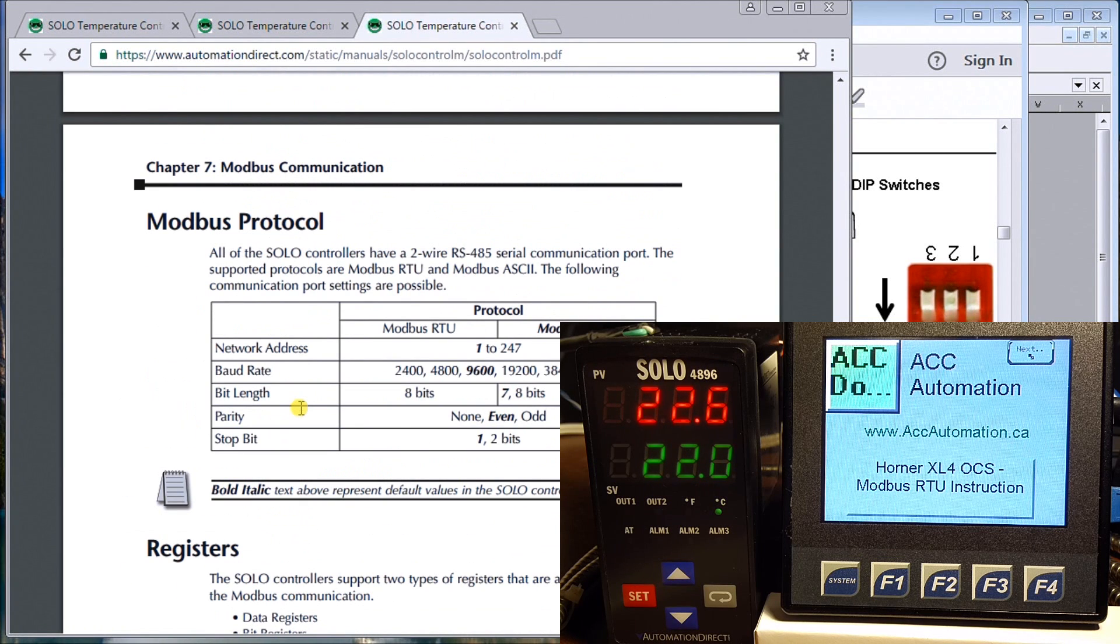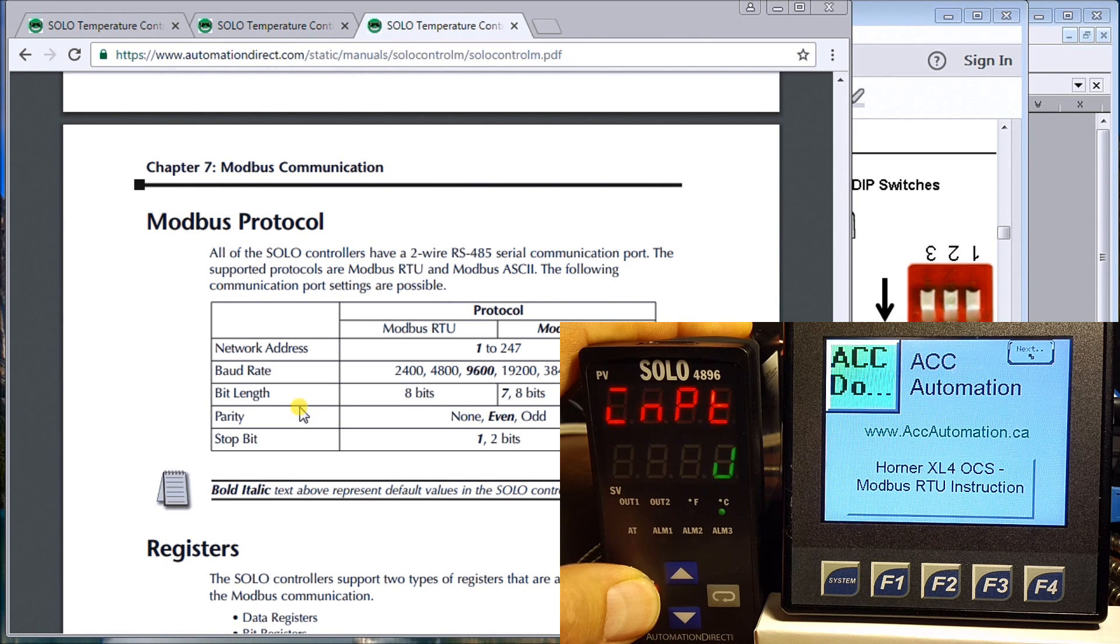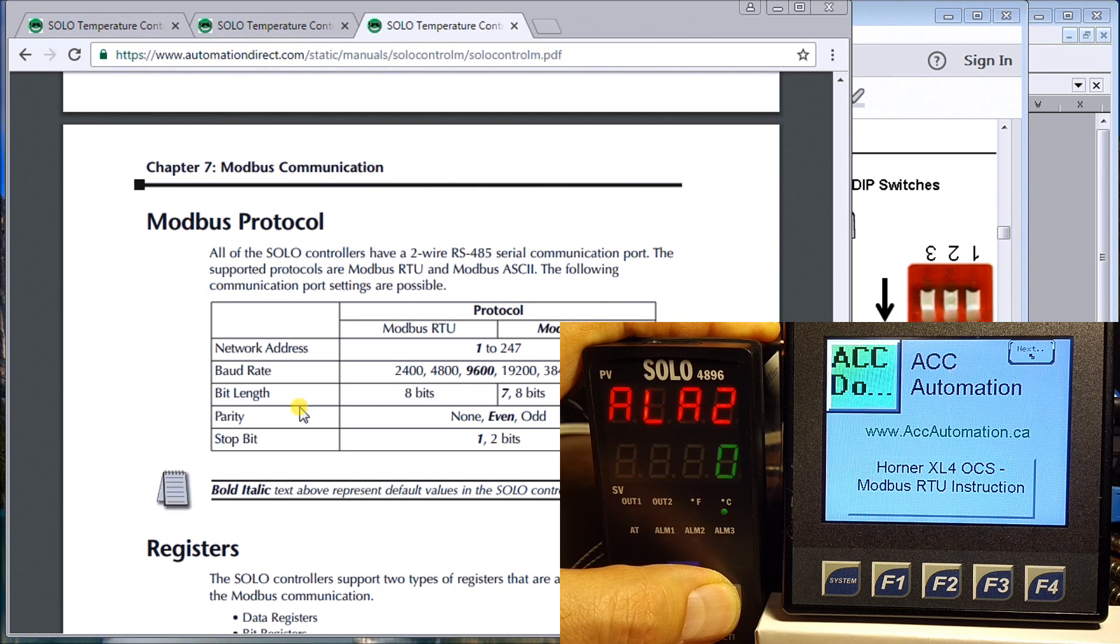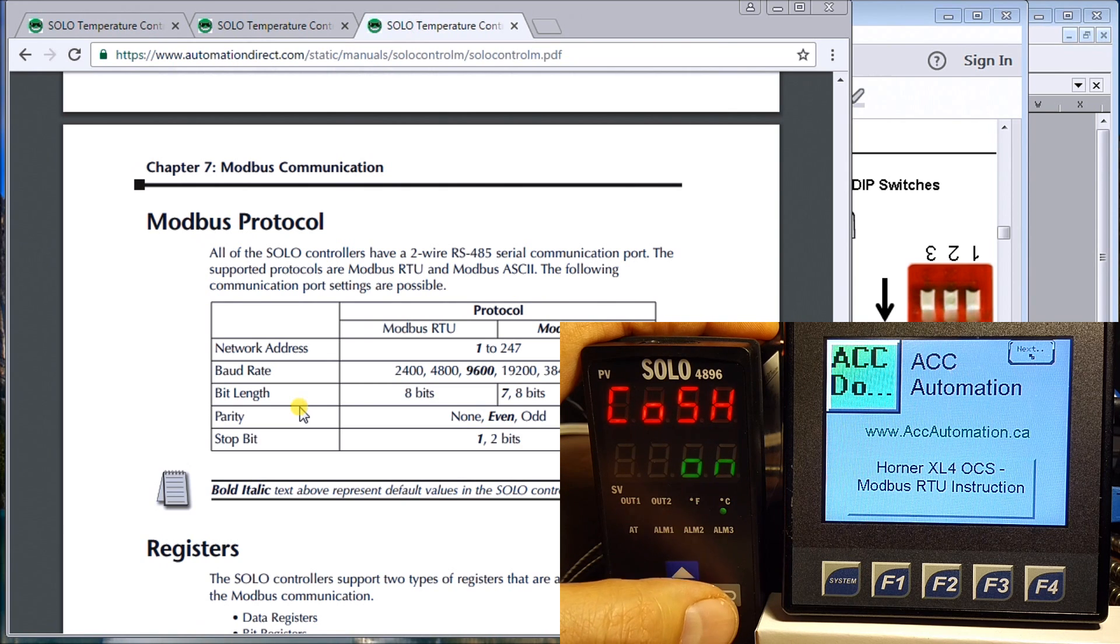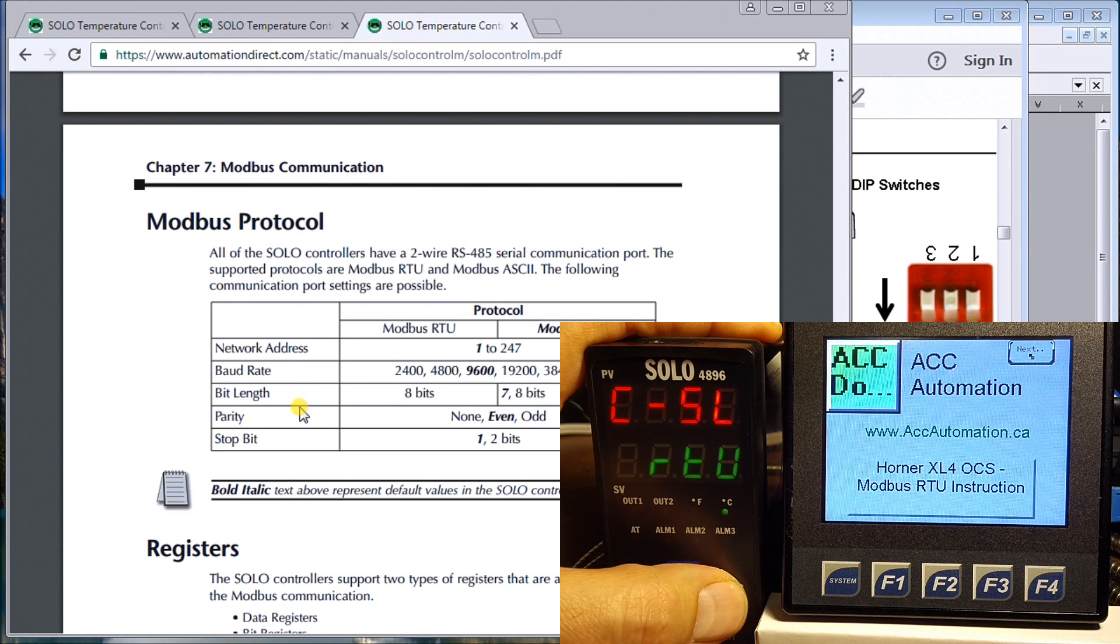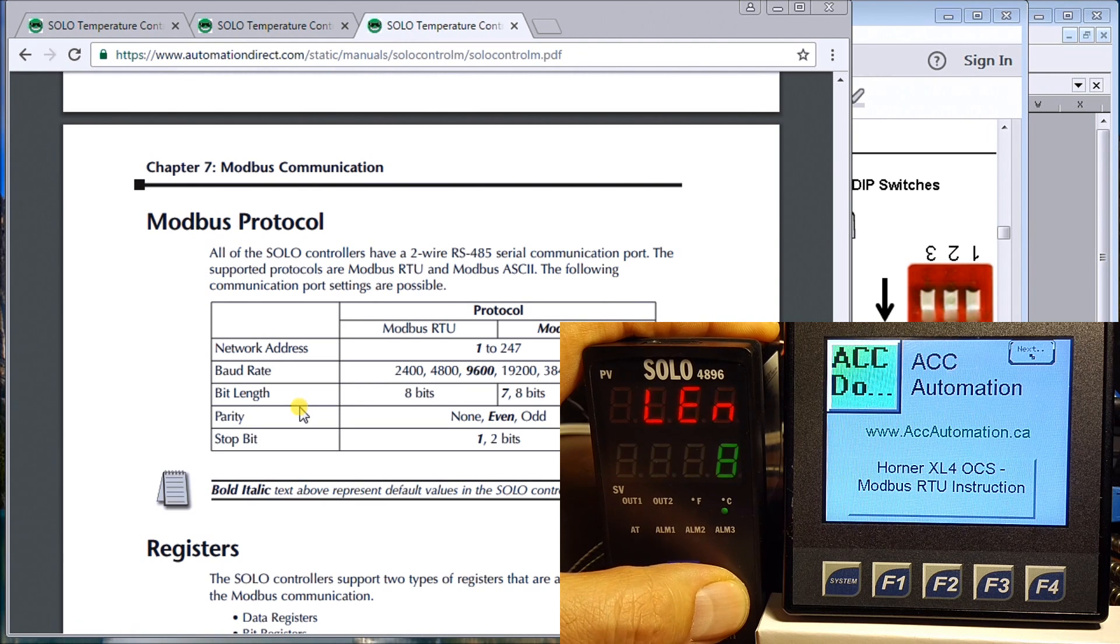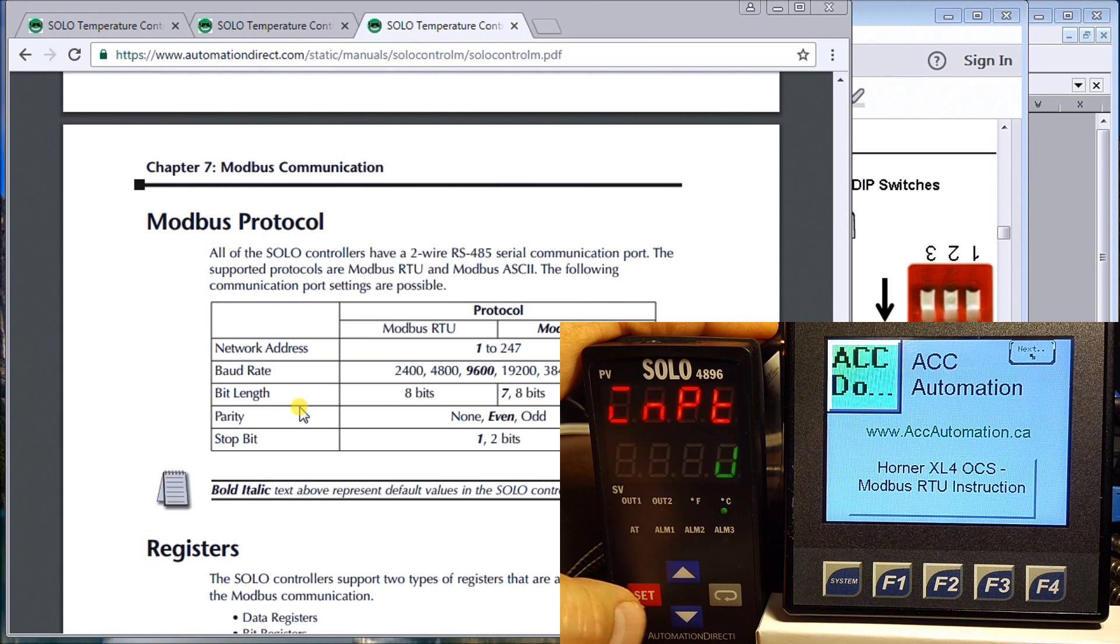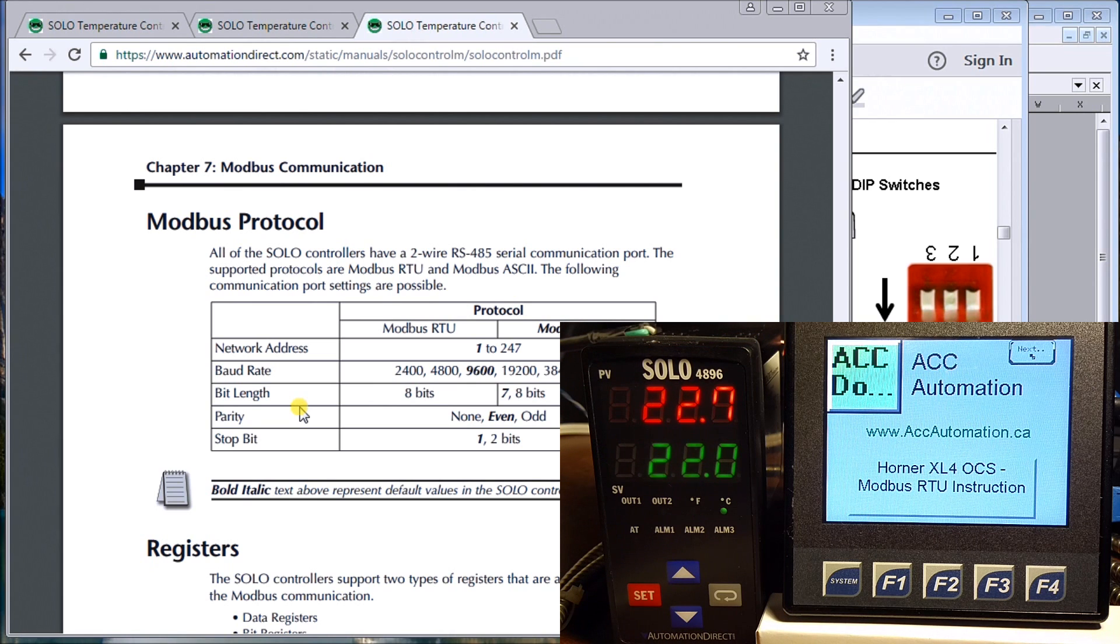On the SOLO, if we hit and hold SET, we will come up with the parameters. What we want to do is go to the first setting, which has to be displayed as ON. That enables us to communicate to the SOLO through the communication port. Then we have the setting for RTU for Modbus, unit number one, 9600 baud, length is 8, even parity, and one stop bit. Those are all the settings we need to do for the SOLO. We'll put that back in run mode.